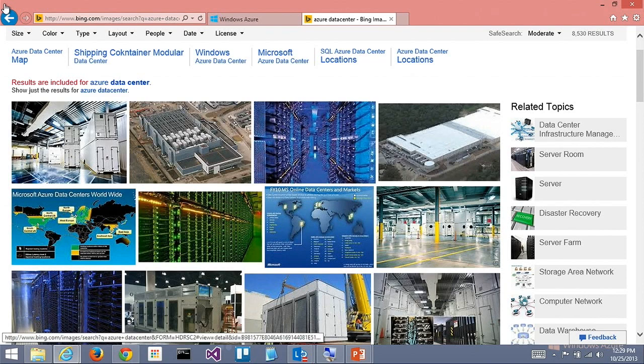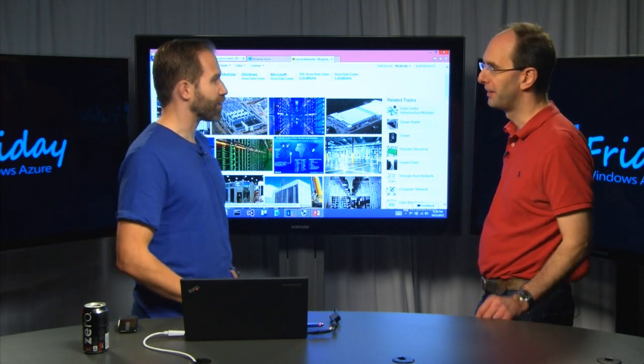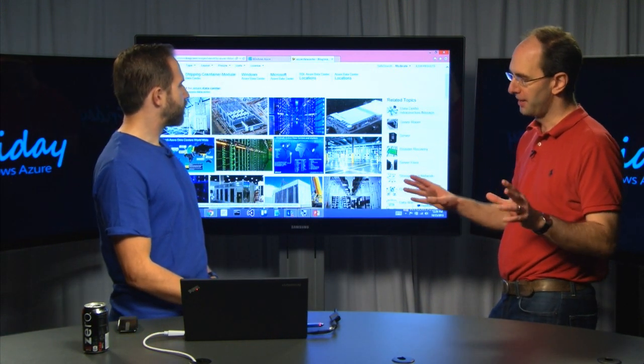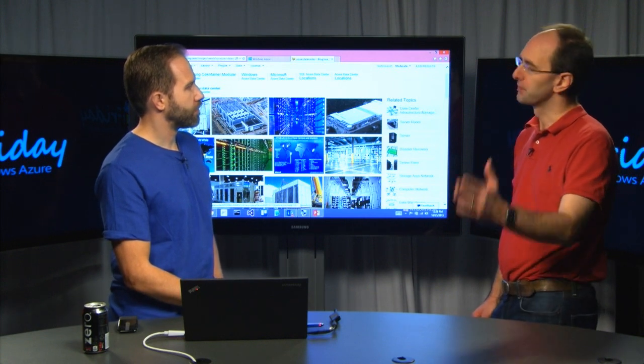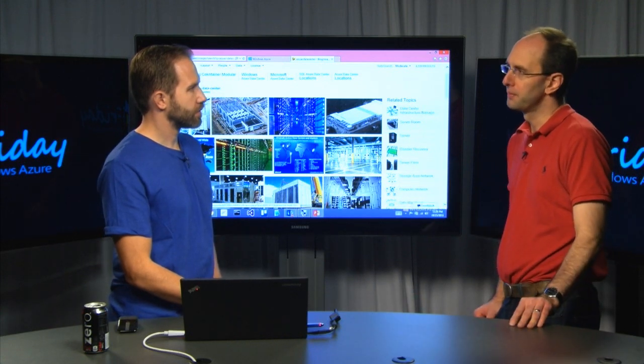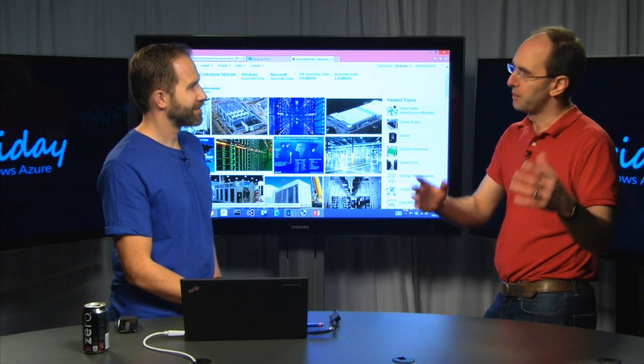Within a data center, depending on the region, there might be what we call colos, or actually firewall-separated regions within it — for physical fire protection, not security. Literally, this part of the building goes away, that part's fine. A typical data center will have firewalls in the physical sense. If there was a bad fire, the firewall is usually rated for about four hours to survive, so the fire department could arrive and put it out. With an area this big, if there was a disaster, how do you contain it?